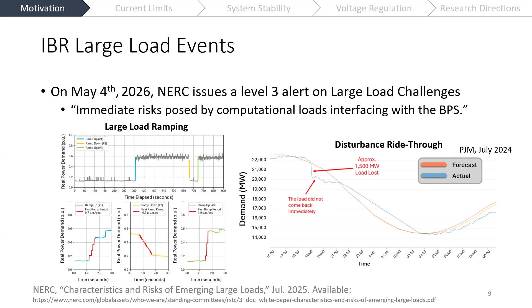And also the fact that these data centers are prone to tripping or disconnecting from the grid and going to their own backup resource anytime there's some issue with the quality of voltage in the grid, or if they think something bad is happening there. To prioritize their own reliability, they might just disconnect. There's an event here where 1,500 megawatts of data center load disconnected from the grid all at once. Luckily, the system operators were able to handle that fault and keep the system stable. But it shows that having these devices that can quickly disconnect from the grid provides even more of a challenge for the reliability of the bulk power system.